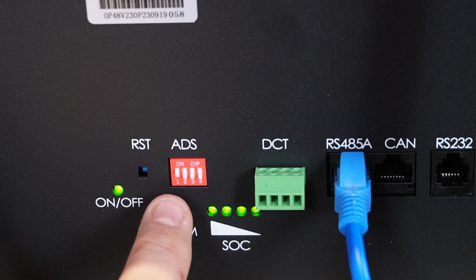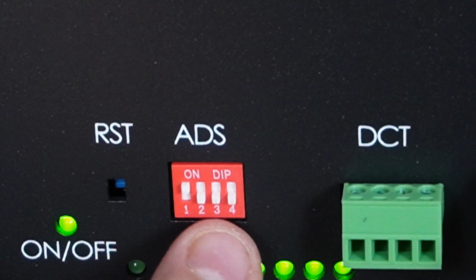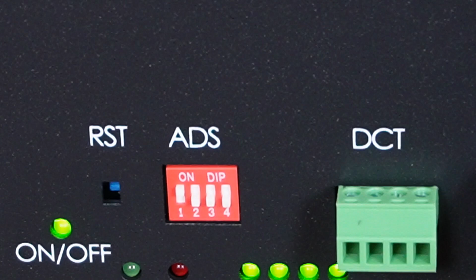These are dip switches here that you set depending upon how many batteries you're running. The way it's set right now, the first one's in the up position and the others are in the down off position. That means this is either the master battery in an array of batteries that are paralleled together, or if it's standalone. The way I've got it set right now is the battery is standalone.